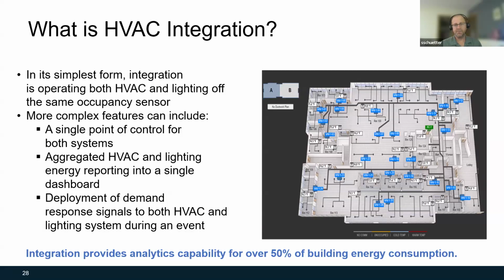It's not uncommon today for a building to have multiple control systems, both for lighting and HVAC, and sometimes even multiple systems for each. In its simplest form, the integration of lighting and HVAC provides the ability to control lighting and HVAC from shared occupancy sensors. With a single point of control for both systems, shared schedules can be implemented, providing synchronized behavior of the light and temperature levels based on predetermined scenes as well as occupancy status.